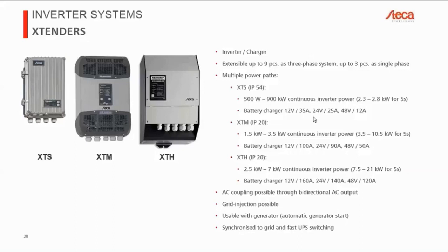There's 12 volt, 24, and 48 volt models that we have, but they are separate. So you cannot switch from one to the next because, of course, the transformer on the inside is suited to your battery. So depending on which model you choose, you have different battery charging currents. That's just the maximum value. You can program that in the device itself. The XTM is pretty much the same thing. Here we have an IP20 housing, higher powers, and of course, higher charging powers as well.